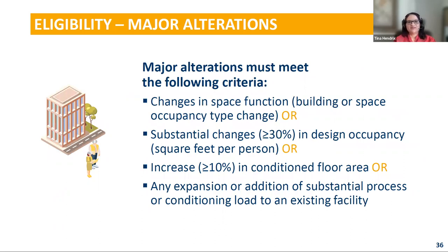In terms of major alterations, think full gut renovation - not just a lighting retrofit or a paint or carpet change out. In addition to that full gut renovation, you also have to meet one of these: either a change in space function - say going from manufacturing to warehousing, or office space to multifamily apartments - or a substantial change of greater than 30% in design occupancy, square feet per person, or an increase of greater than 10% in conditioned floor area. Not all three, just one of these. The last bullet point refers to agricultural or industrial projects where there's an expansion or addition of substantial process or conditioning load to an existing facility - think adding a conveyor belt, a physical plant, things of that nature.